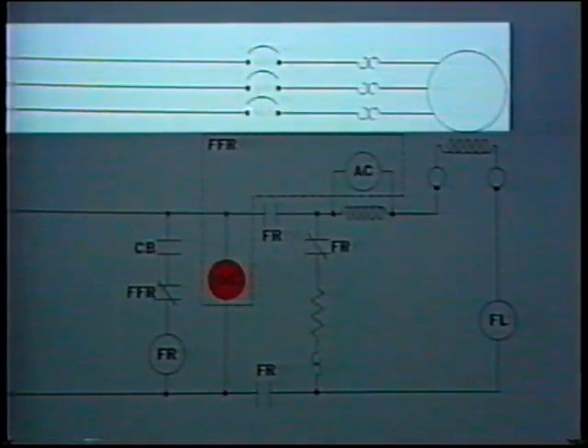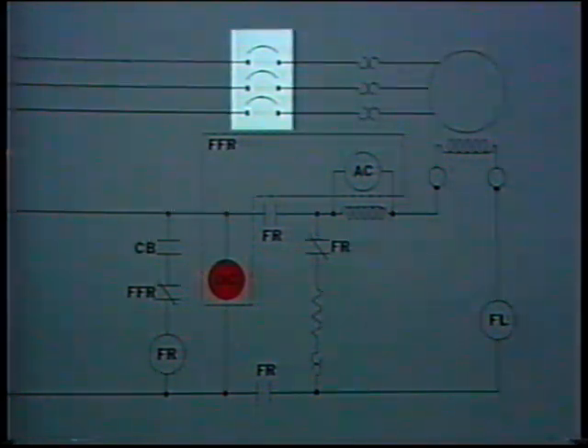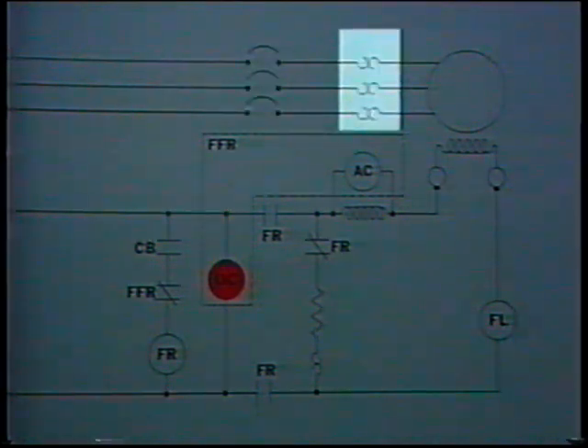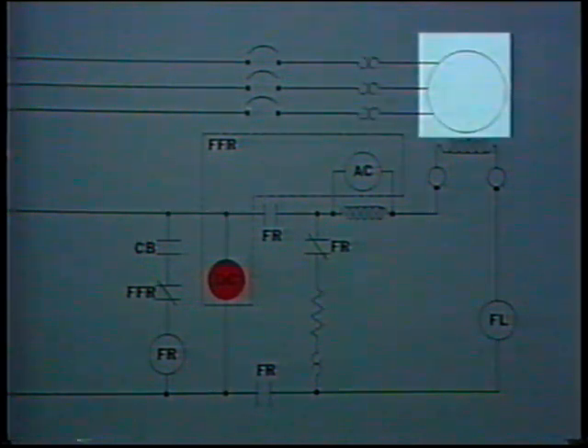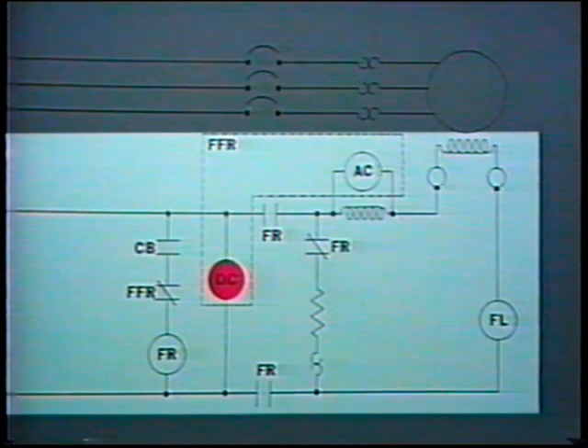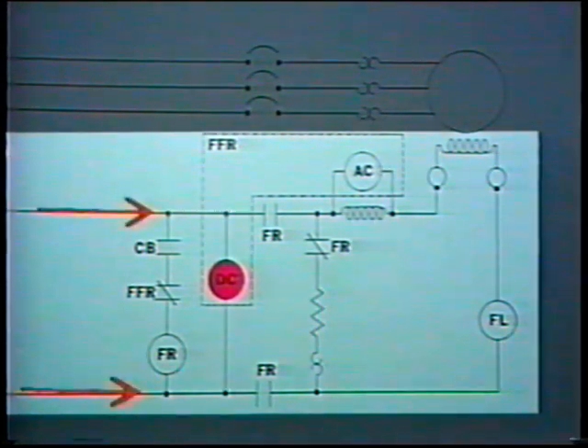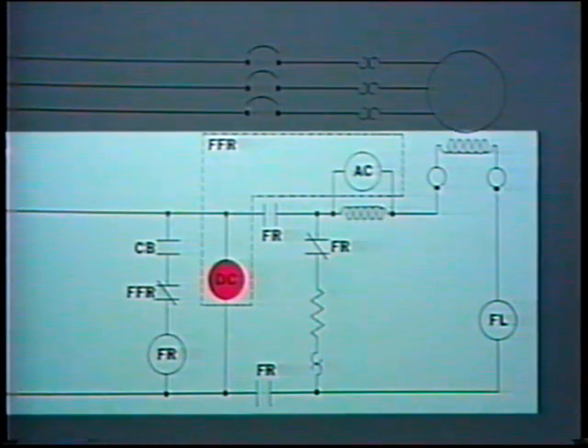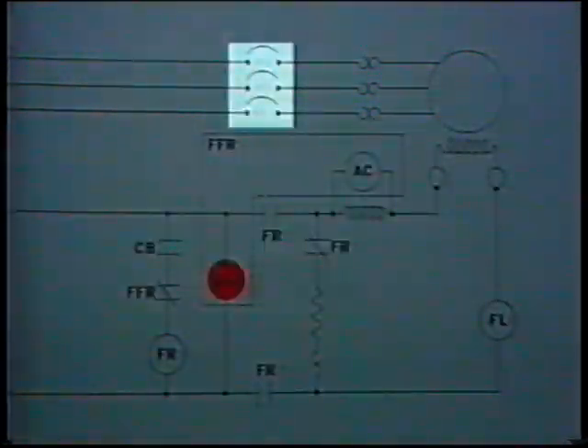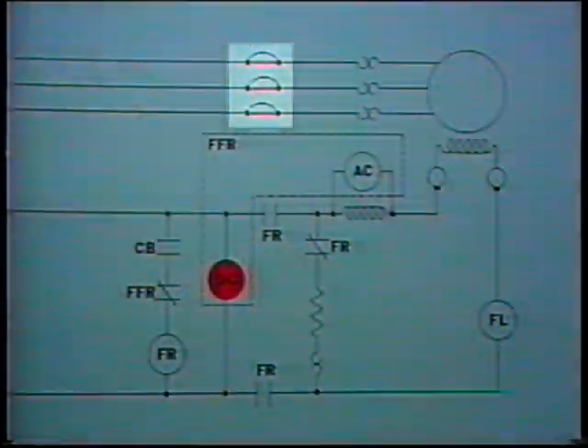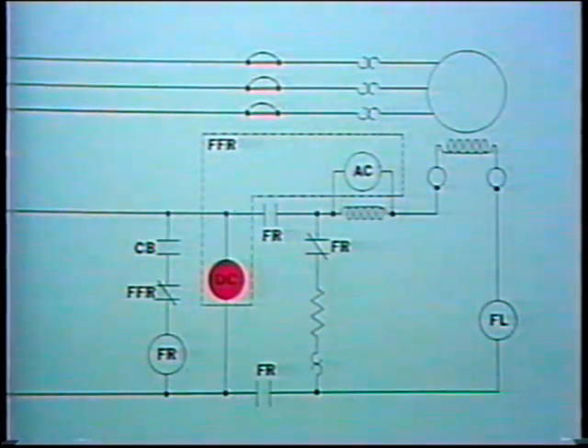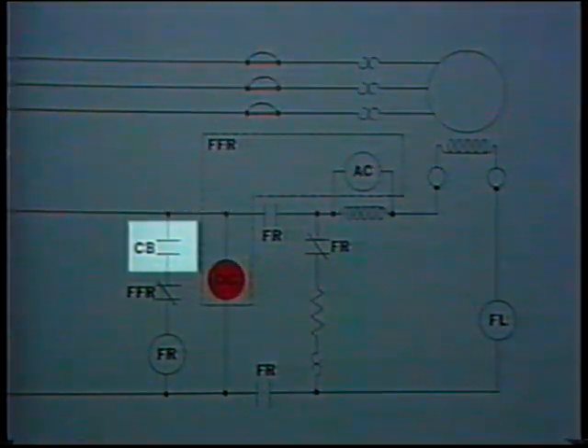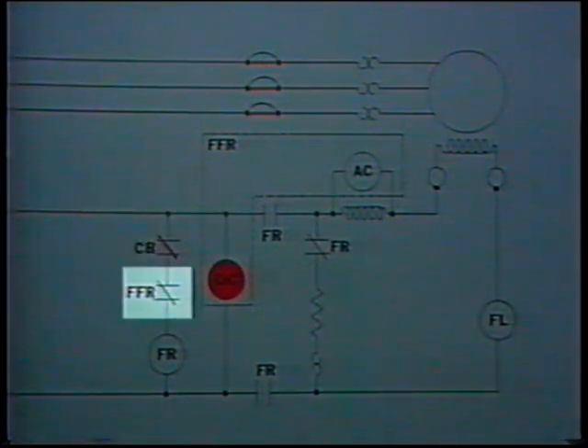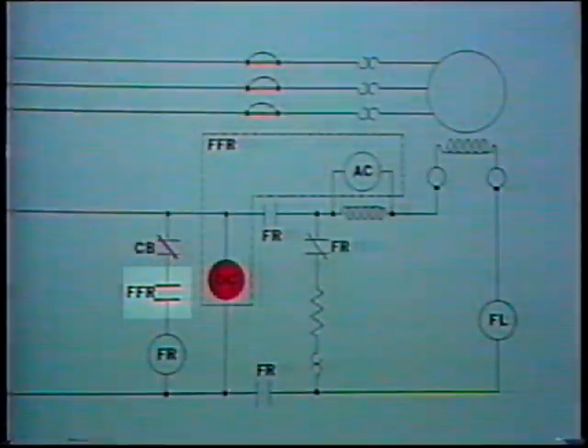The stator circuit contains 3 line leads, a circuit breaker, 3 overload heaters, and the stator windings of the motor. The rotor circuit contains the DC power supply, a number of relays and contacts, and the rotor windings. When the circuit breaker is closed, alternating current flows from an AC power supply through the stator windings of the motor. Closing the circuit breaker causes these contacts to close. At the same time, these contacts open. We'll see why that happens in a minute.